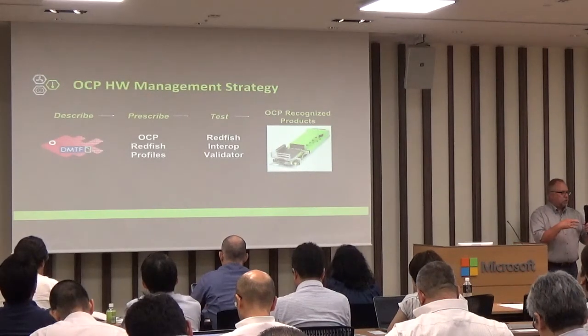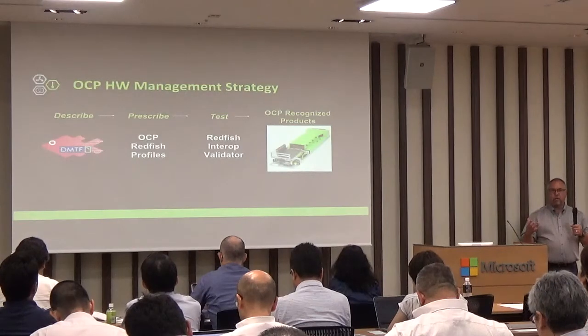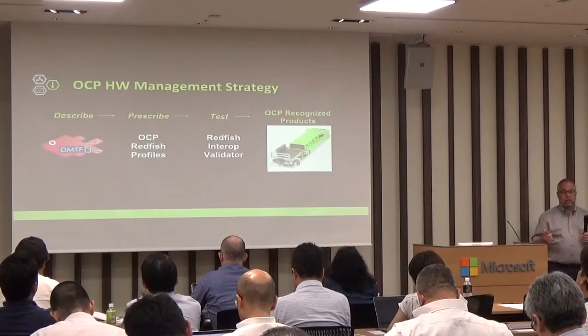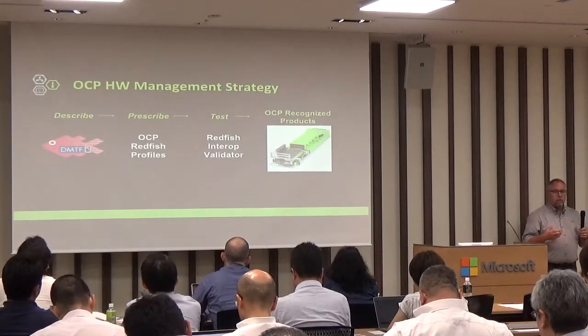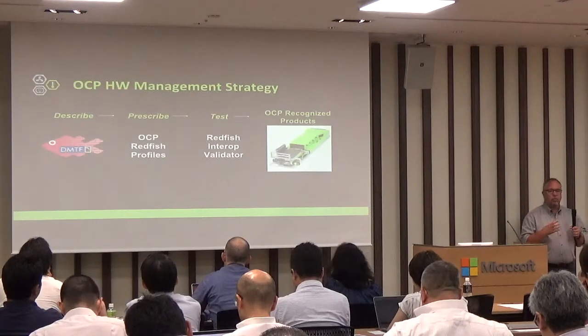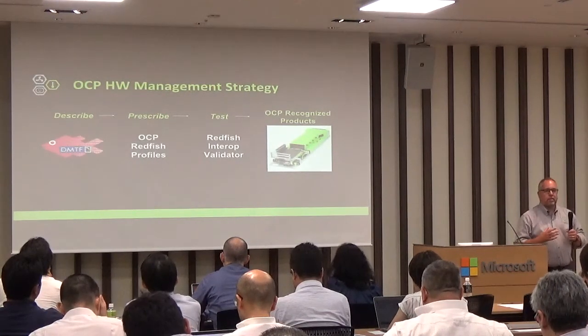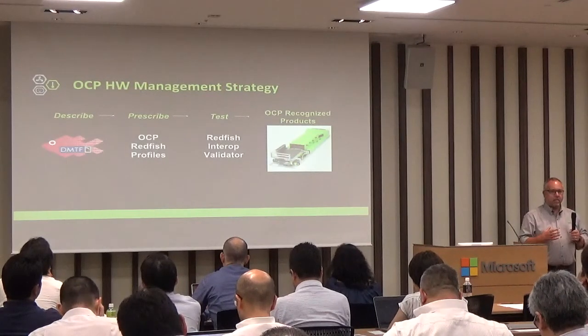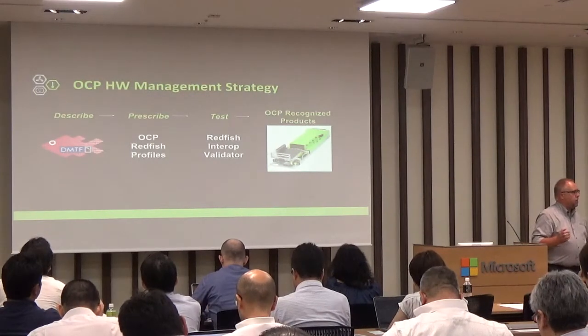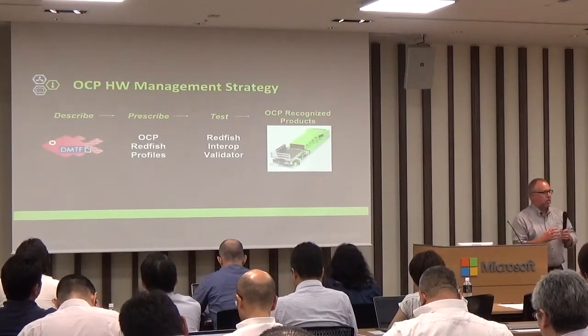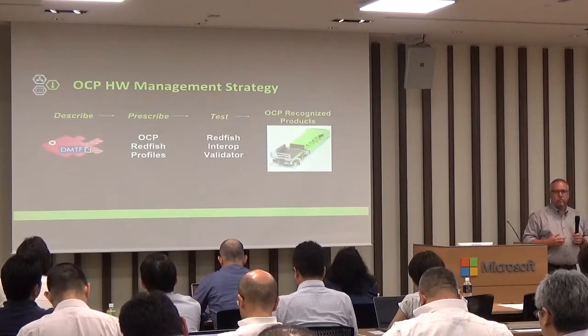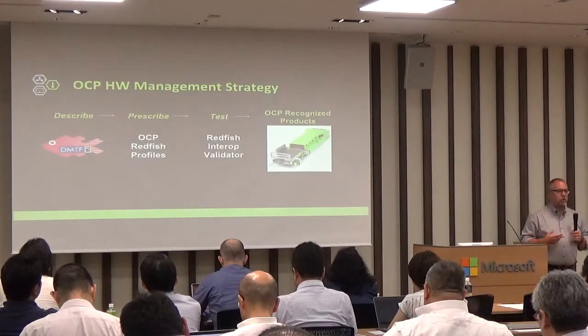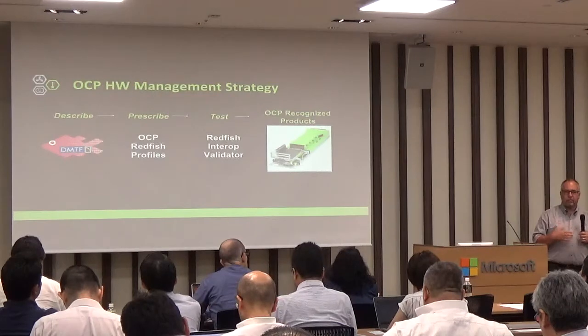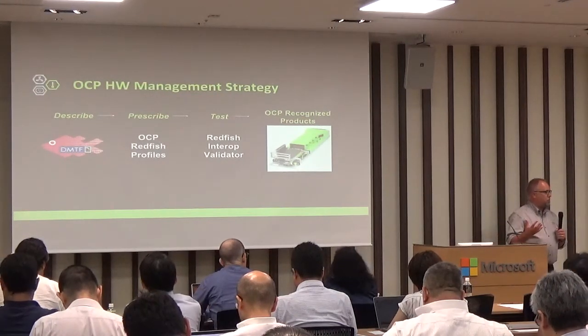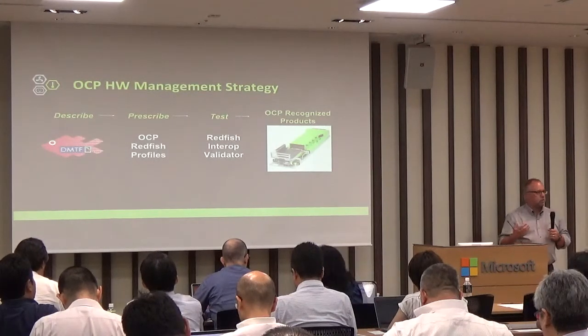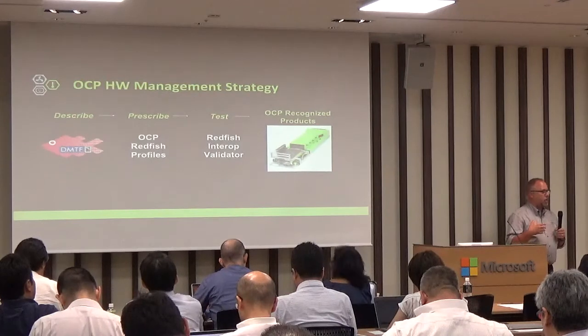The DMTF organization has written a specification for Redfish, so we don't need to write anything. But what we do need to do is prescribe how we use Redfish. They've written and released specifications on which properties need to be supported by which devices. The idea is that if you buy a server, regardless of who you buy it from, it has the exact same support and is interoperable with other manufacturers' equipment. They've defined that in a specification called the OCP profile - we have a baseline profile, a server profile. And to test equipment, we're fortunate that DMTF has created a validation test, an interop validator.